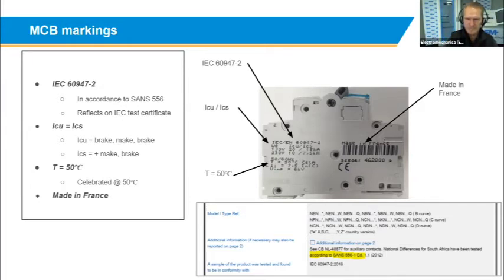So I think what's supposed to happen is that when there was a short circuit on the application, you actually need to make a note of it. And then after the second or third short circuit the product has seen, the best is to replace it, because each time the fault level will drop on the product. And that's on all products, even on molded case circuit breakers, you'll see a similar rating on it.